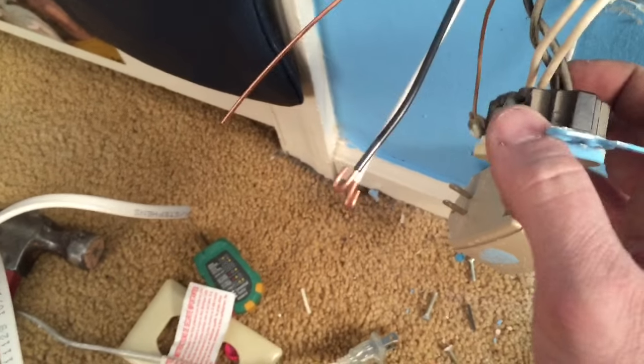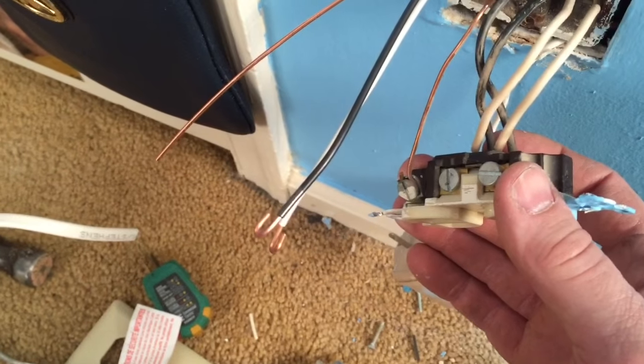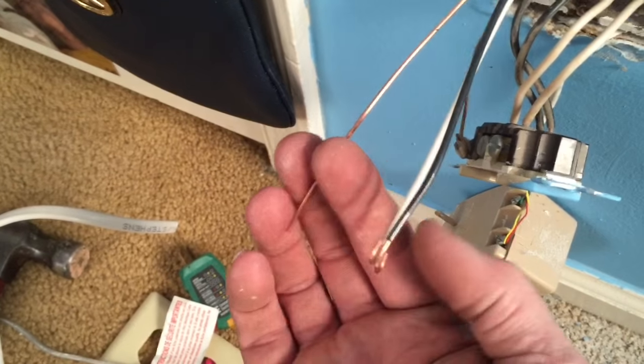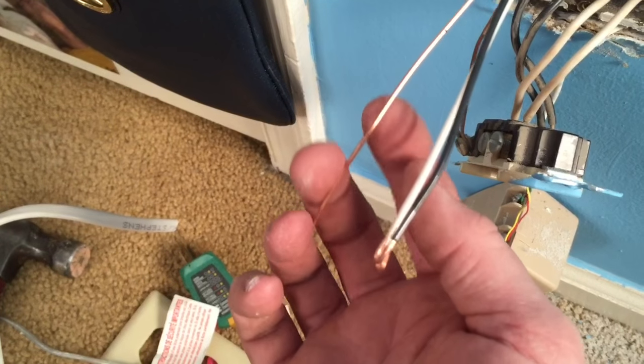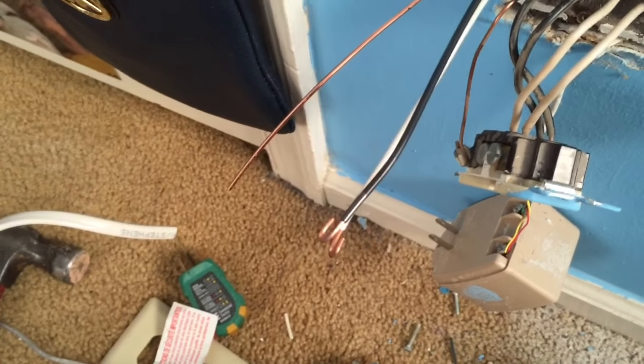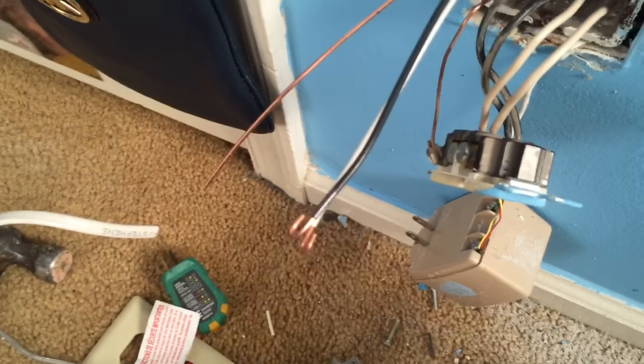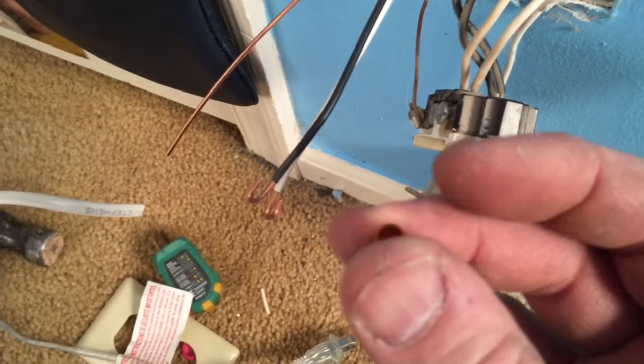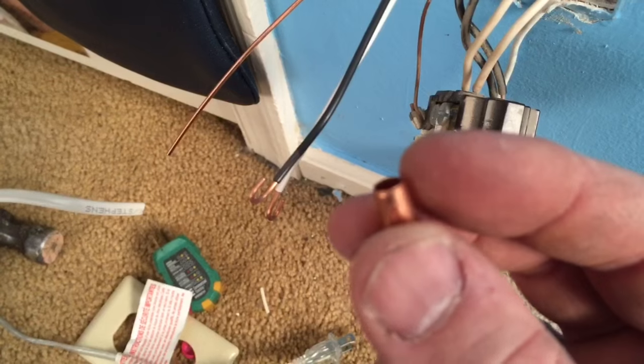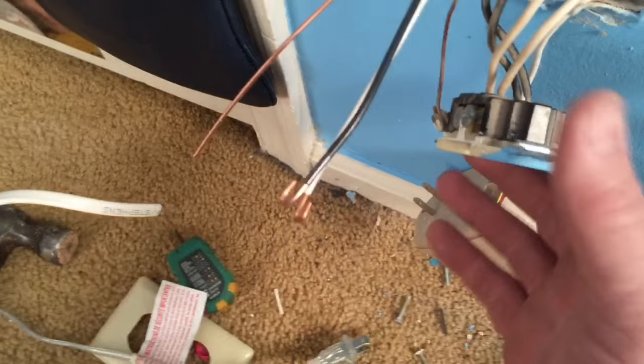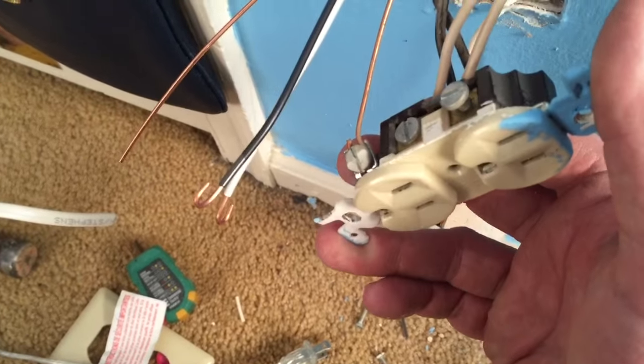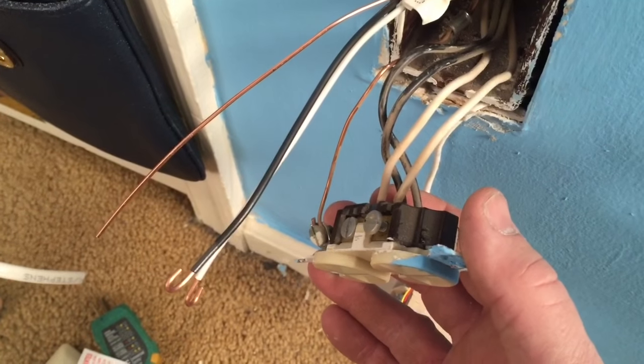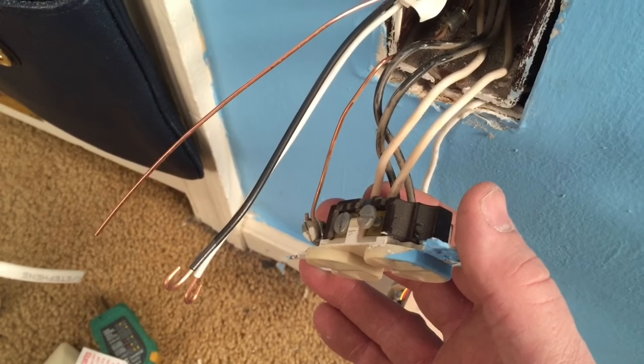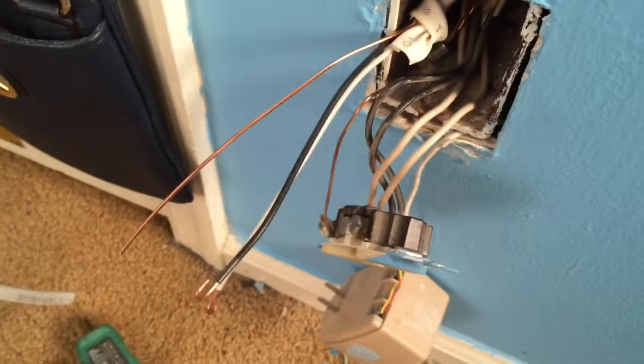And our ground wire down here on the outlet, we're going to take that loose, and we're going to twist our ground wire around that wire and install this little copper crimp, and we will crimp that nicely, and then we will reattach our ground onto our outlet here. So let me make all those connections, and then we will go up top and get the new outlet installed.